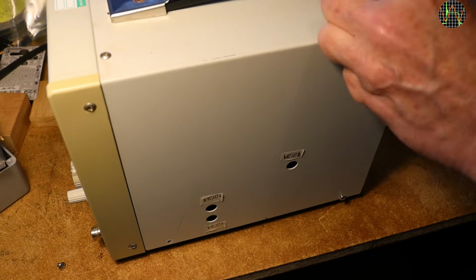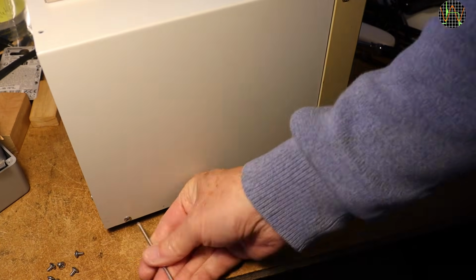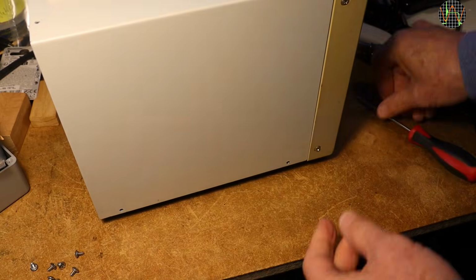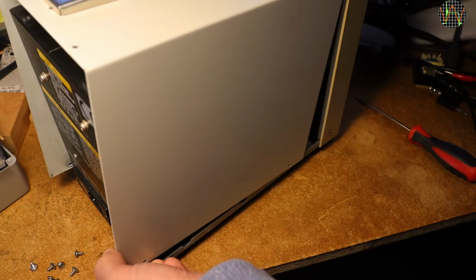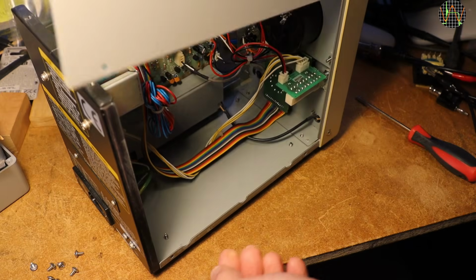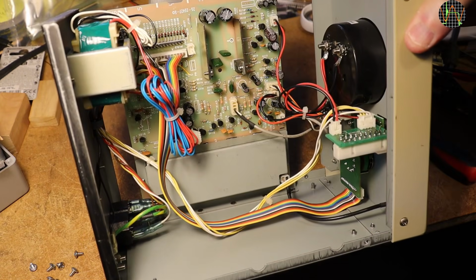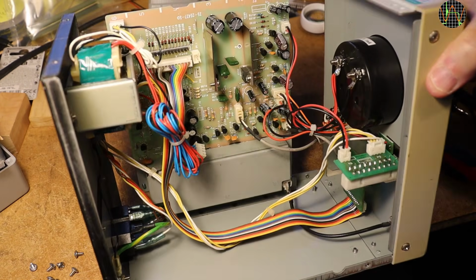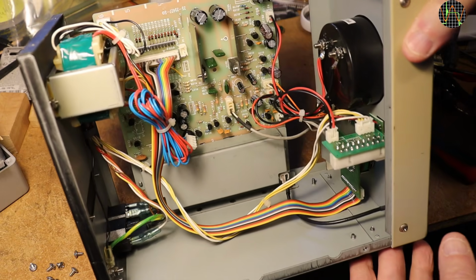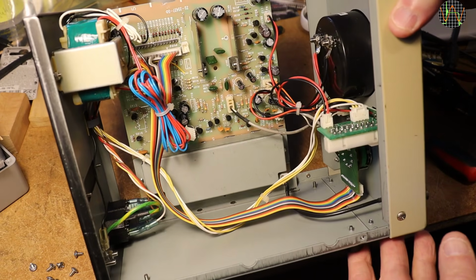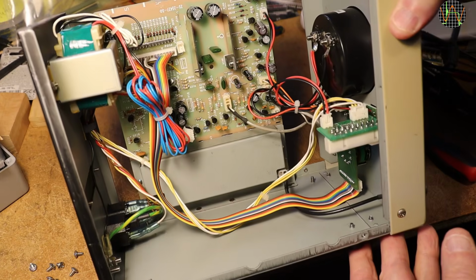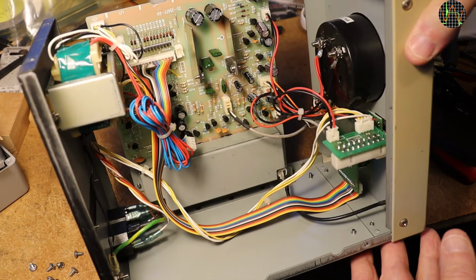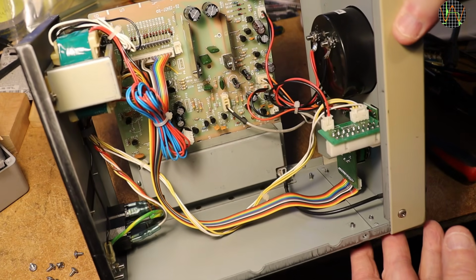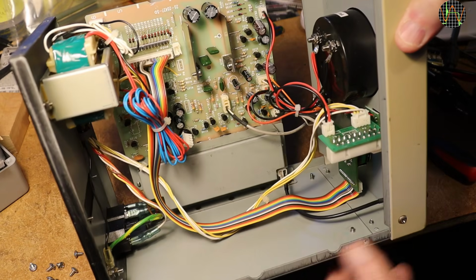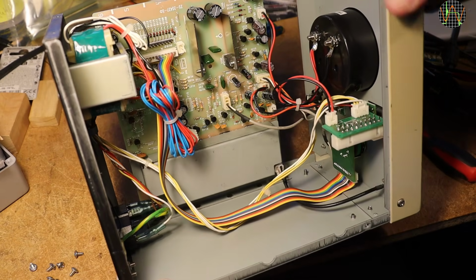Lots of screws to open the case, 2 on the side, 4 on top and another 2 on the other side. With that, the U-shaped cover comes off and reveals the inside. The transformer on the rear, a PCB with a shielded section on one side wall, and the instrument and range selector on the front. The enclosure leaves room for another PCB on the other side wall, for example, for a model providing 2 input channels.